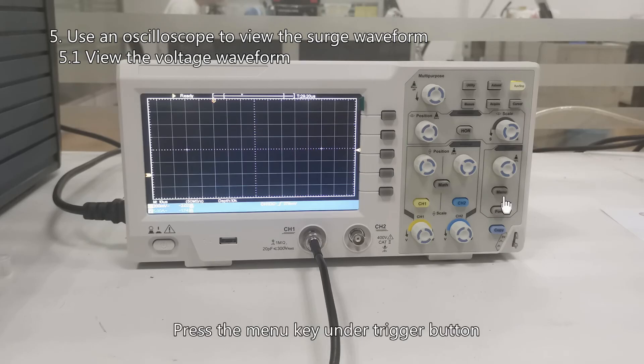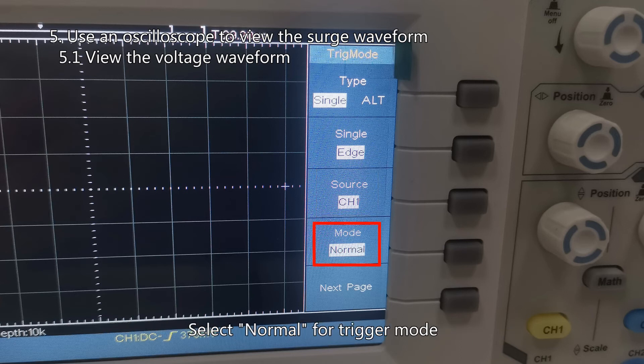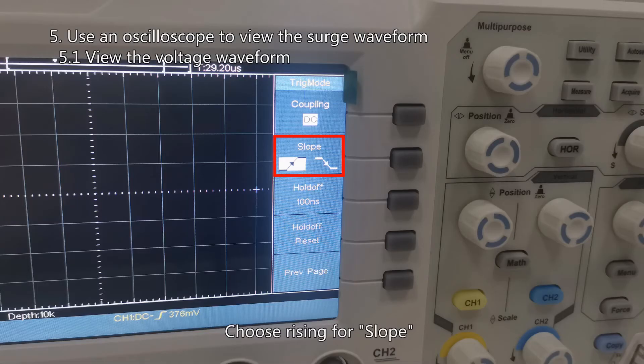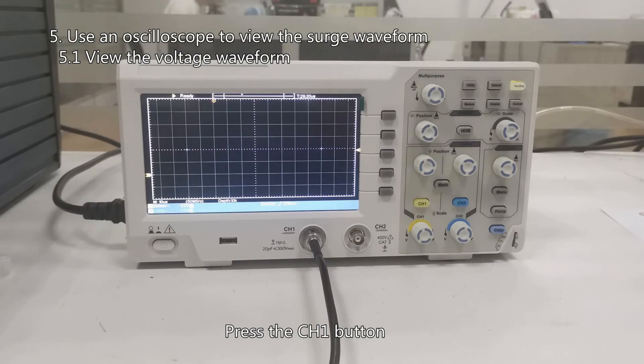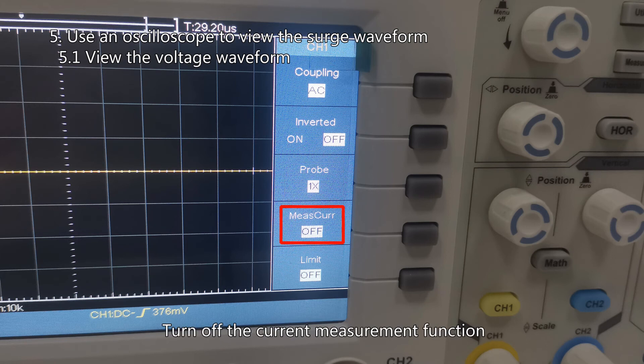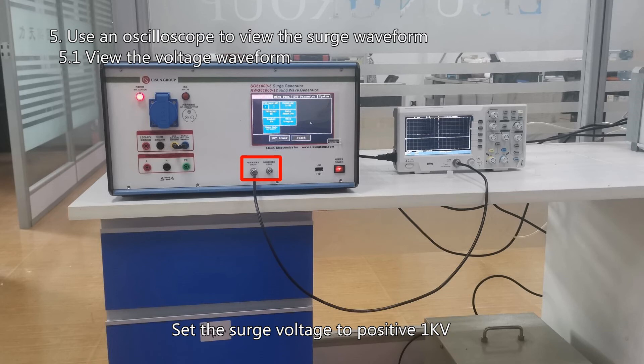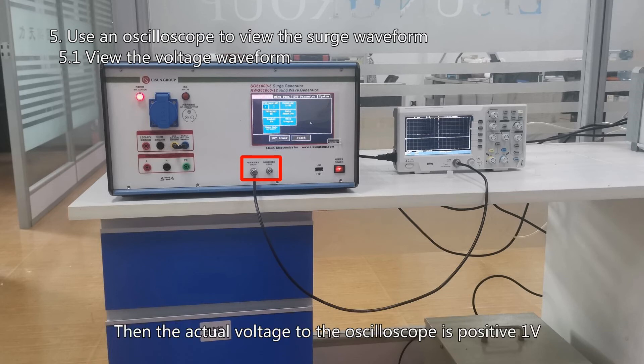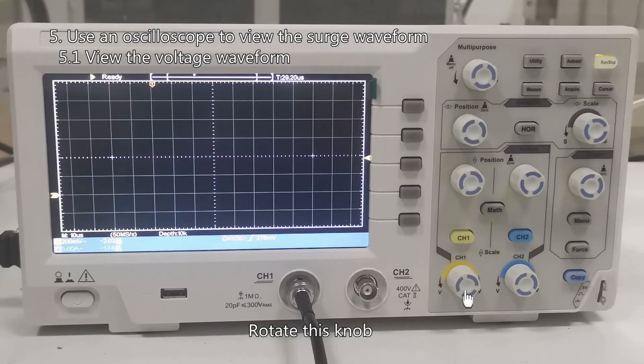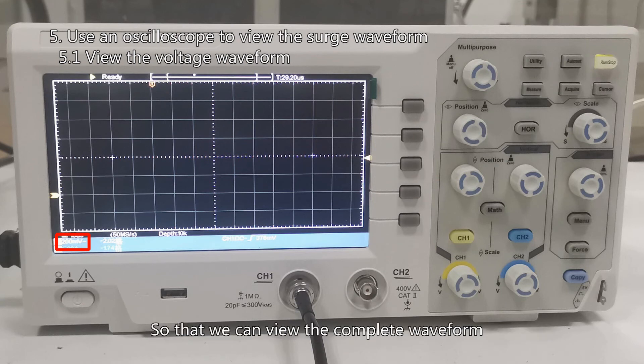Turn on the oscilloscope. Press the menu key under the trigger button, select the corresponding channel for the signal source, and select normal for trigger mode. Click to the next page and choose rising slope. Press the CH1 button and set the probe multiple to 1x. Turn off the current measurement function. The Lisun surge generator has a built-in 1-to-1000 high voltage probe at the oscilloscope interface. Set the surge voltage to positive 1 kV — the actual voltage to the oscilloscope is then positive 1 V. Set the vertical axis to 200 mV per division to view the complete waveform.